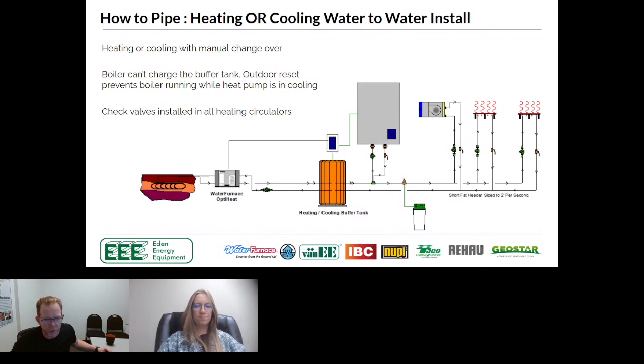So what's going to happen is your unit is going to immediately shut off. It's going to lock out on high pressure. And if you continue to let it do that, you're going to cook the system, quite literally. So I'm trying to think of a good example to give you. I guess the easiest example would be, we just had Thanksgiving. You put your turkey in the oven, you put it to 500 degrees, and you just leave it there for 2 weeks. What's the outcome?